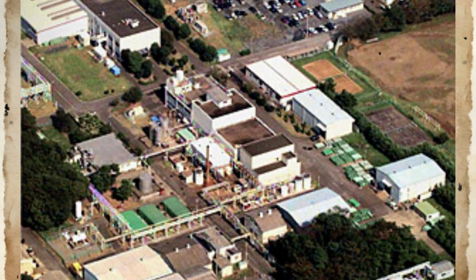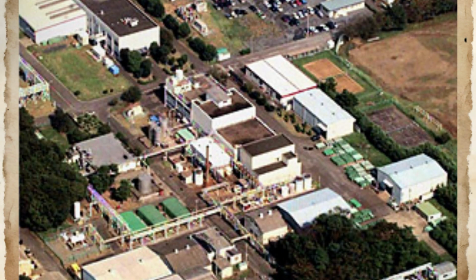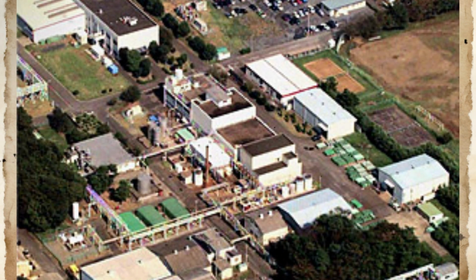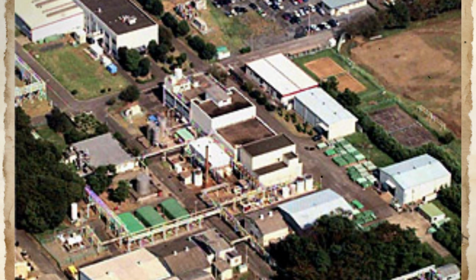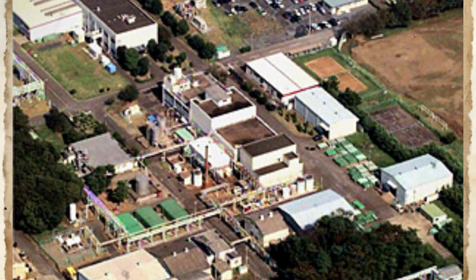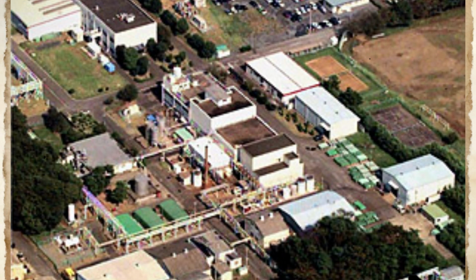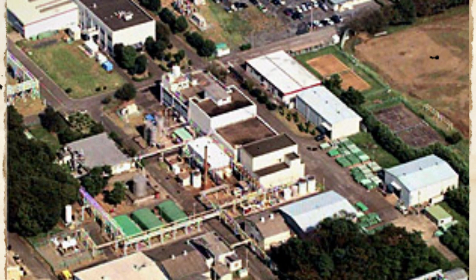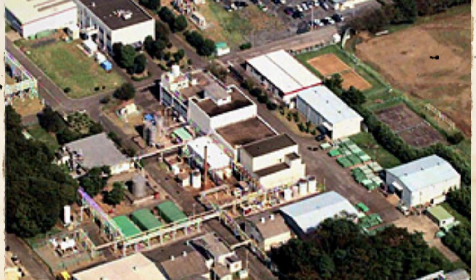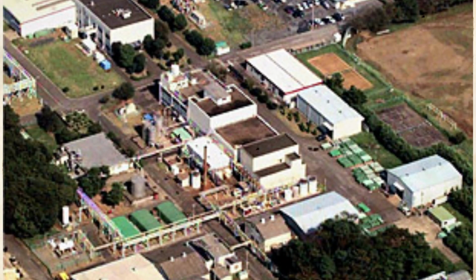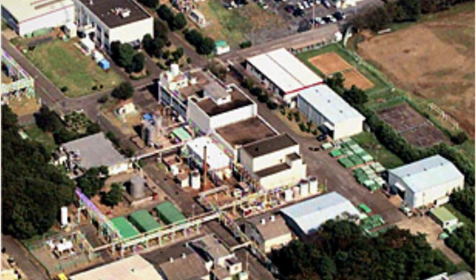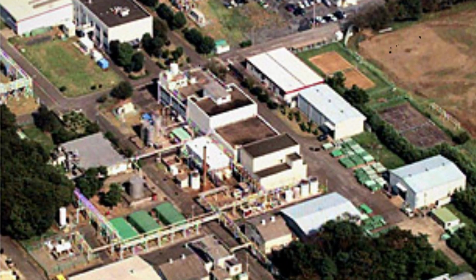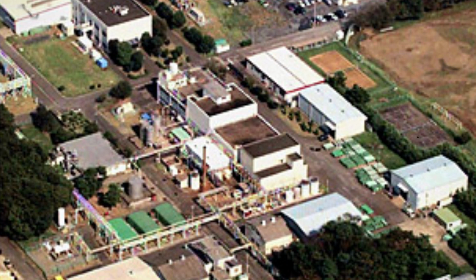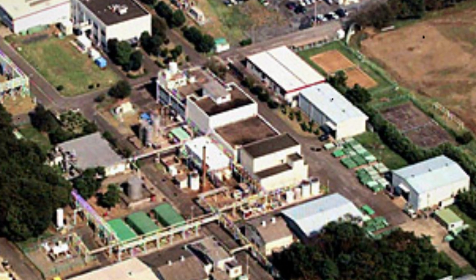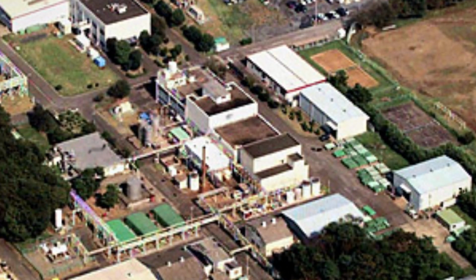This training approach had proven effective for developing operator expertise in managing the types of emergencies that had been anticipated by the design process. However, the training scenarios shared a common assumption with the design philosophy that operators would retain access to the instrumentation and control systems needed to implement emergency procedures effectively. Training exercises for station blackout conditions focused on the brief power outages that the design basis envisioned, during which operators would manage the transition to emergency power and verify that backup systems were functioning as intended. Extended station blackout, lasting hours rather than minutes, had not been incorporated into the training curriculum because it had not been incorporated into the design basis.